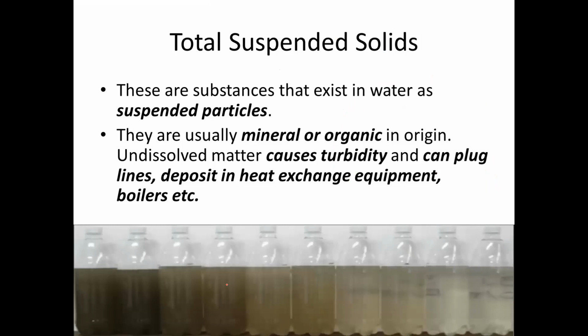So total suspended solids, these are solid substances that exist in water as suspended particles. They are usually mineral or organic in origin. Undissolved matter causes turbidity and can plug lines, deposit in heat exchange equipment, boilers, etc. Yan siya ang tsura, siya ang turbidity. This usually happens when your water has sand particles in it or other organic matter nga nagkaka-decompose sa inyong tubig.